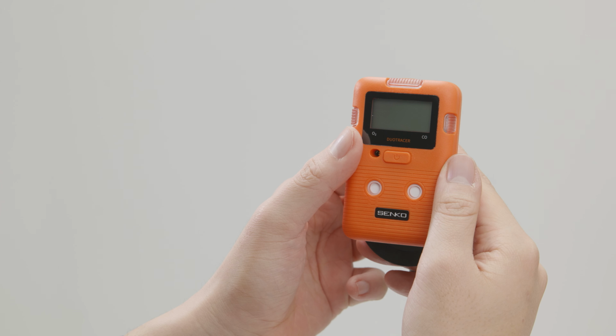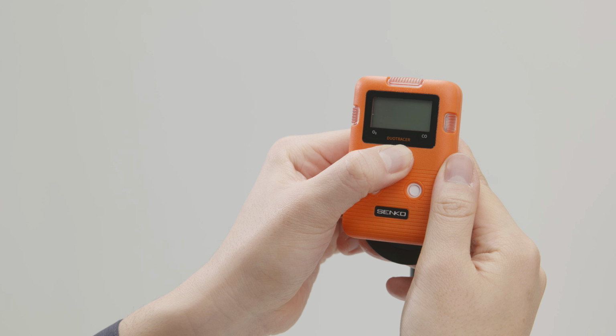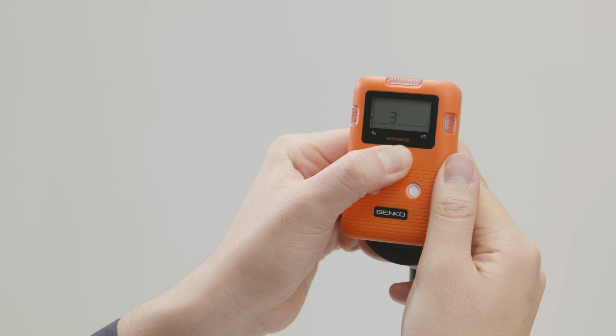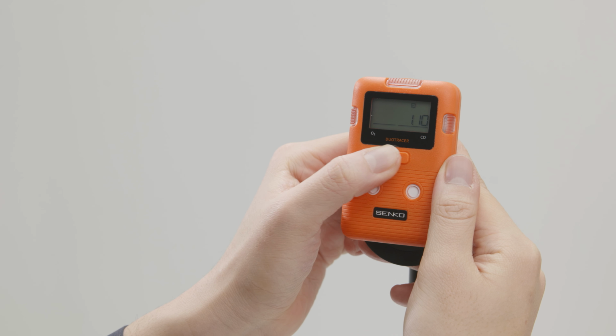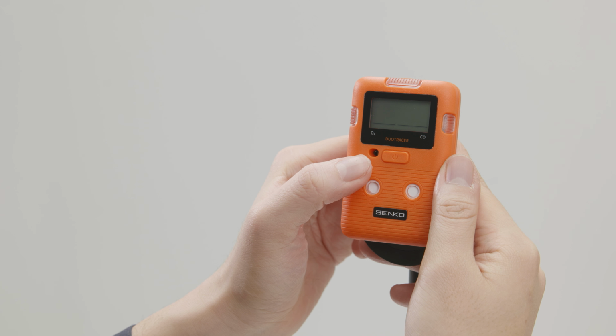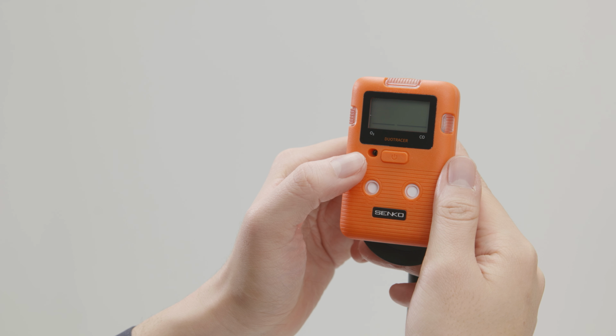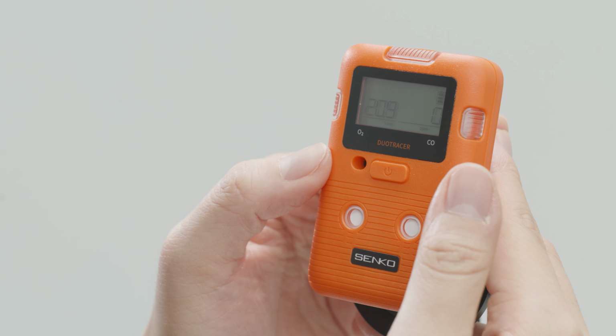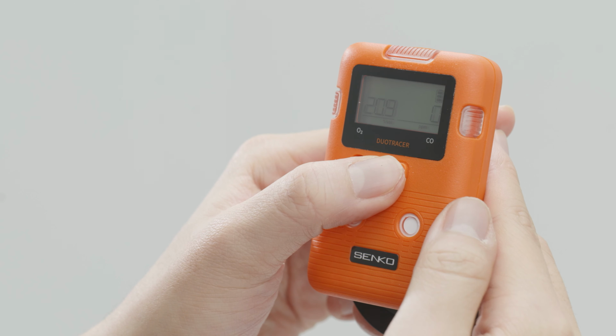So let's see how to use Duo Tracer. To turn on the device, press and hold the button for about 3 seconds. Once the screen turns on, the device automatically runs a self-test, checking sensor status, alarm functions, and display operation. When the self-test is complete, Duo Tracer switches to measurement mode, and the current gas concentration is shown in real time. Turning the device off works the same way.